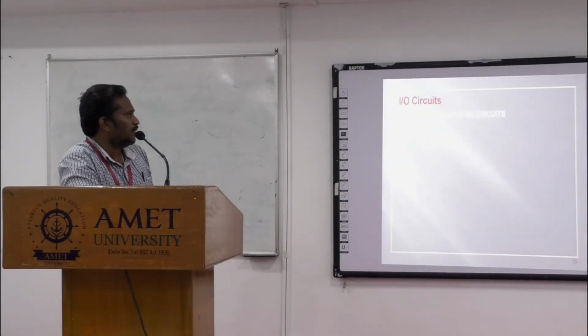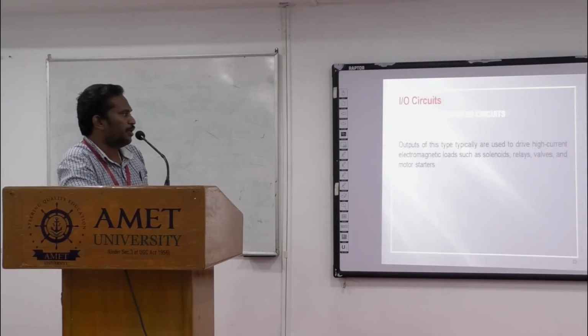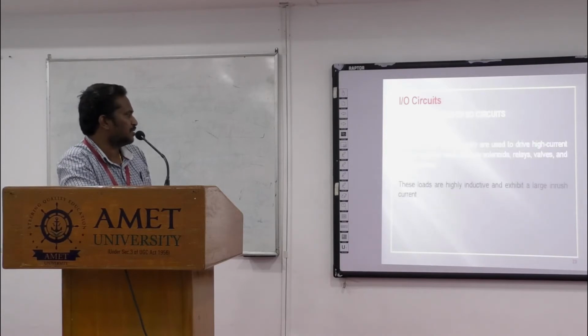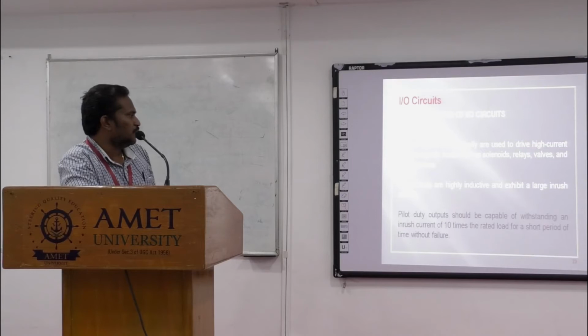I/O circuits, different types of I/O circuits. The first one is pilot duty outputs. Outputs of this type are typically used to drive high current electromagnetic loads such as solenoids, relays, valves and motor starters. These loads are highly inductive and exhibit a large inrush current. So a pilot duty output should be capable of withstanding an inrush current of 10 times the rated load for a short period of time without failure.